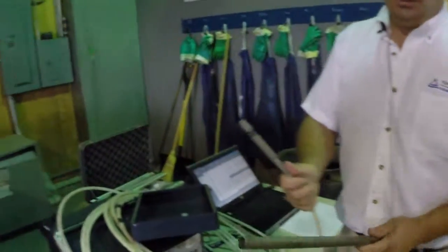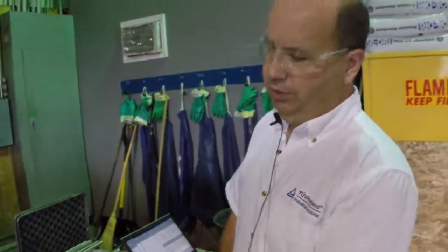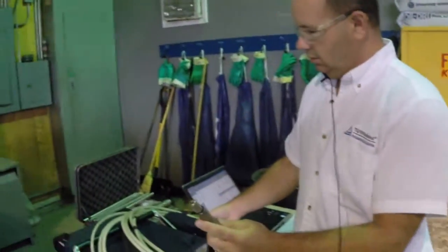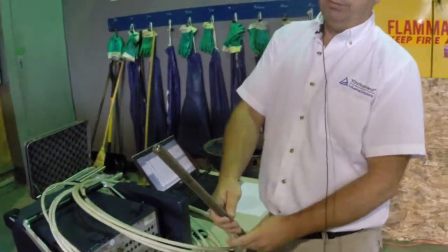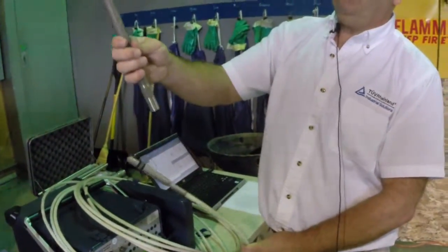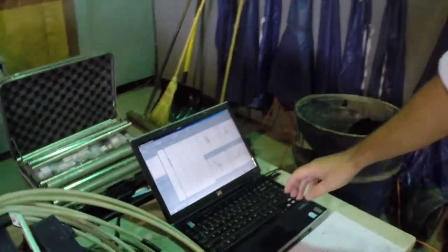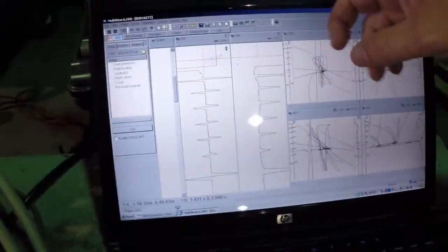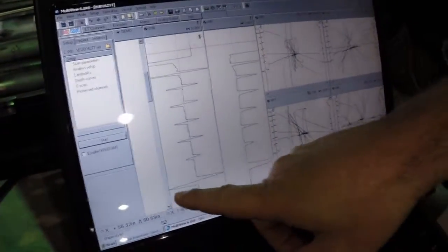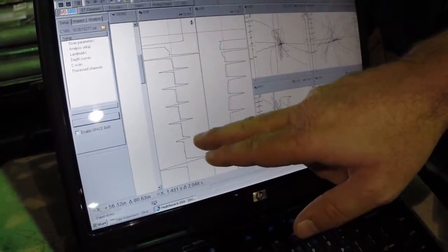The way this is done is the probe is inserted through every tube, or initially through the calibrating tube. What we'll do is we'll start the equipment and pull the probe through. It's being recorded on our machine over here. This would be the signature that we would get from the indications on the tube. Initially, this would be our ID corrosion. This here would be our 100%.